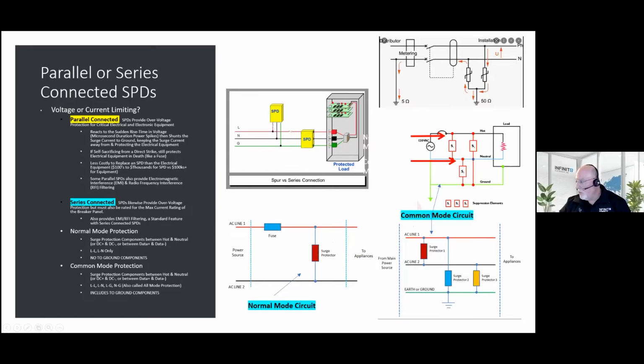So where does the surge current go if there's no connection to ground like here? What happens is the surge component will shunt between the line and neutral, and the surge current will find ground through the neutral to ground bond at the main breaker panel, and to ground from there. So that's how the normal mode protectors work.